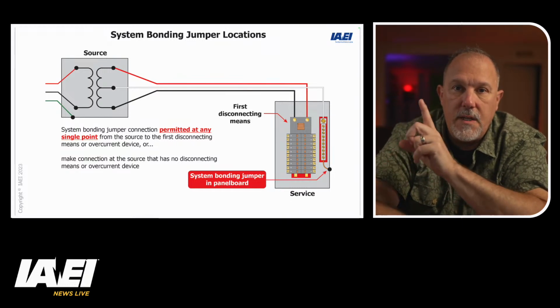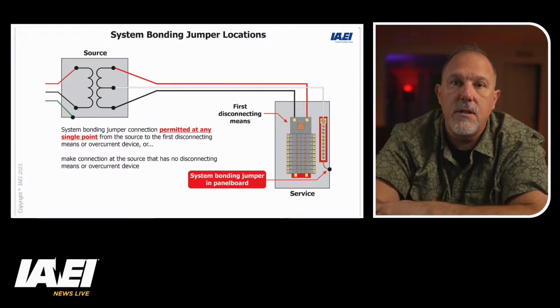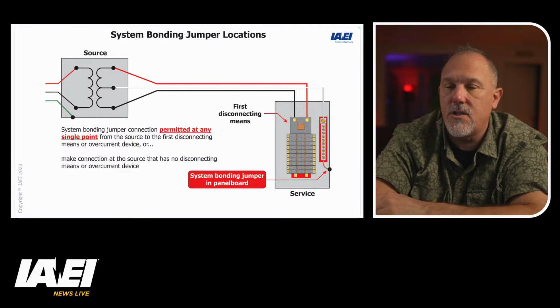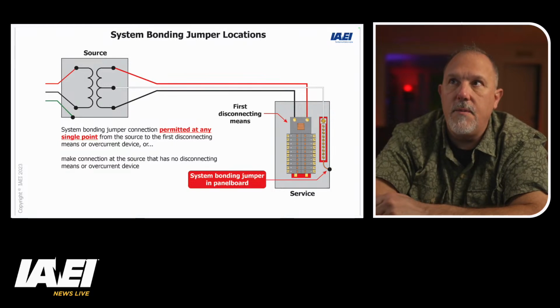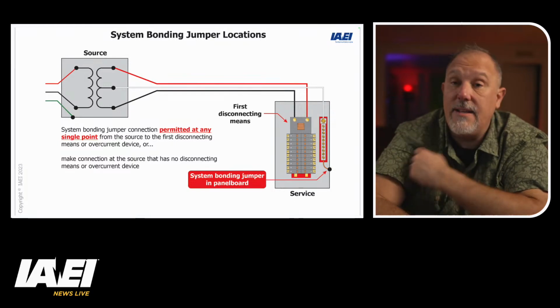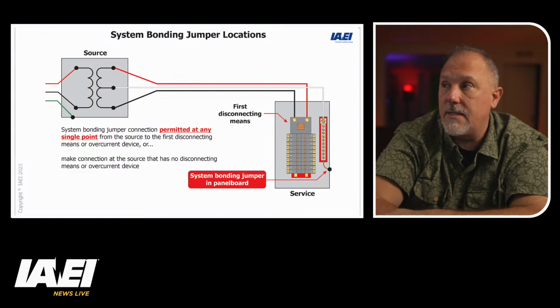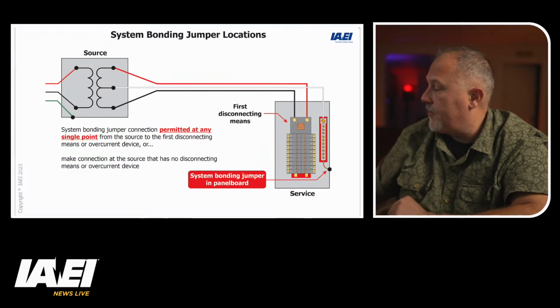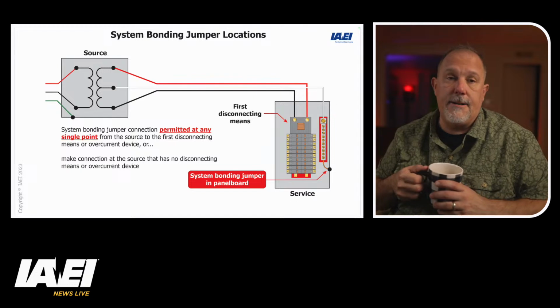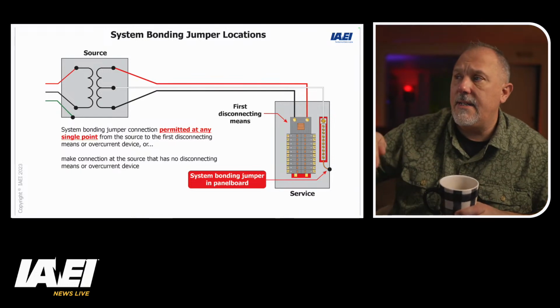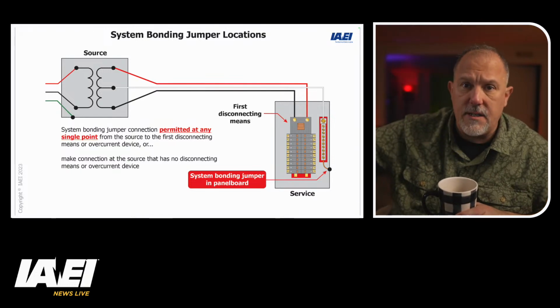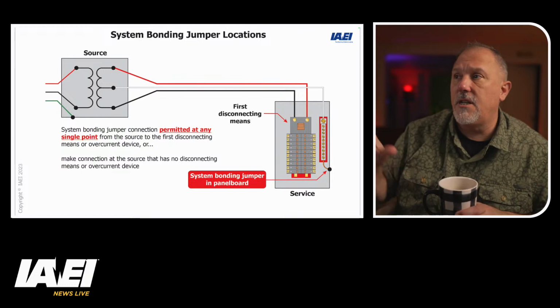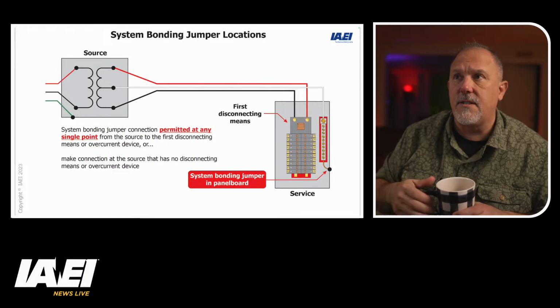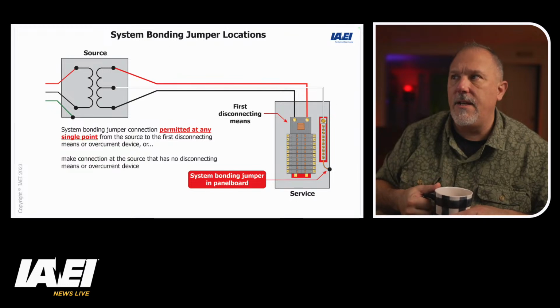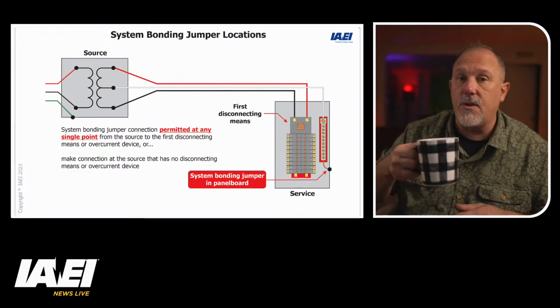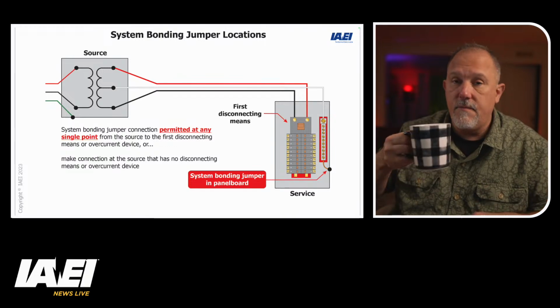Typically, for these transformer applications that are separately derived systems and not service applications, we're going to be doing that in the transformer. That's where I typically see it. I don't know about you guys and gals. I know I was doing a presentation one time, and I showed this example in my presentation. I talked about the grounding and bonding of a separately derived system, and I had somebody raise their hand. They said, we never see it that way. We always do it in the transformer. And that's very valid.